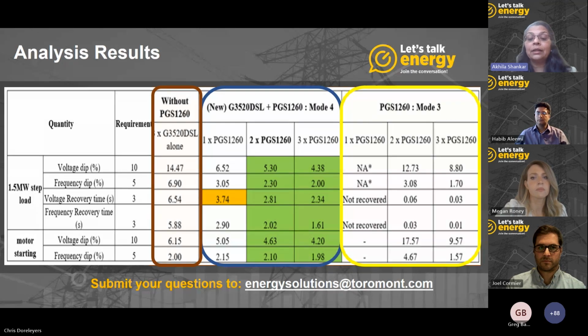The number and the rating of the battery energy storage systems that have to be added with the generator sets to improve the genset transient performance has to be estimated for the specific generator sets and for the given set of site loading conditions. And this is true for all makes and all manufacturers of natural gas gensets.